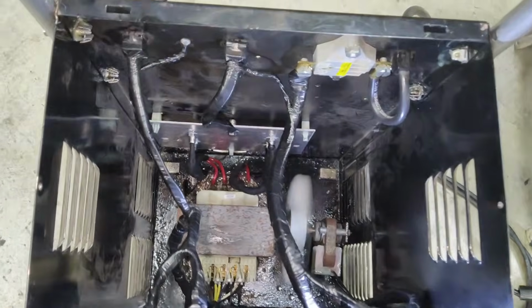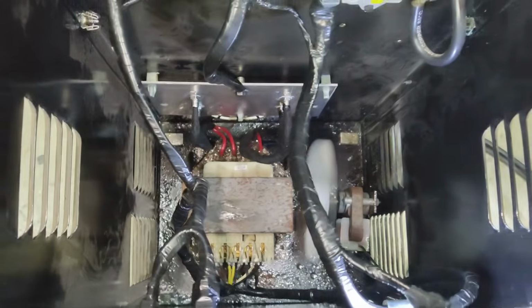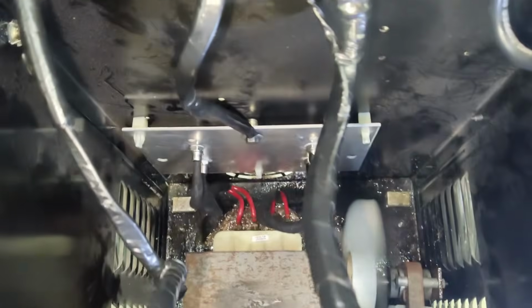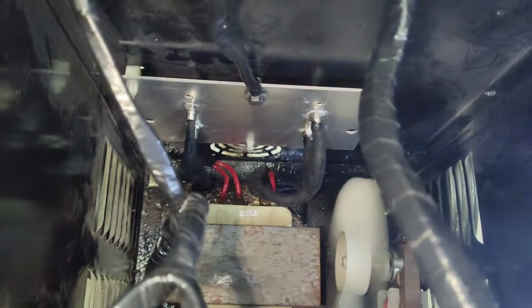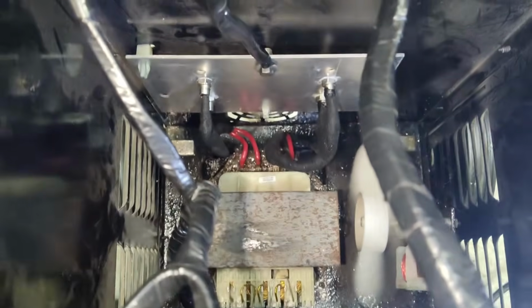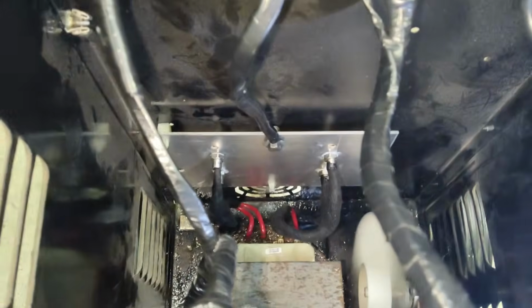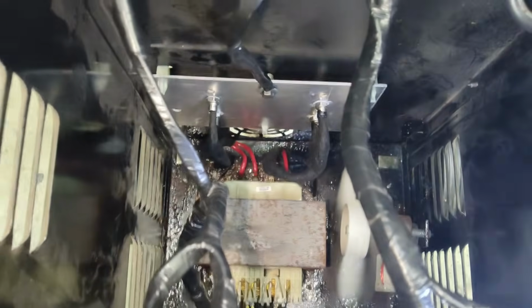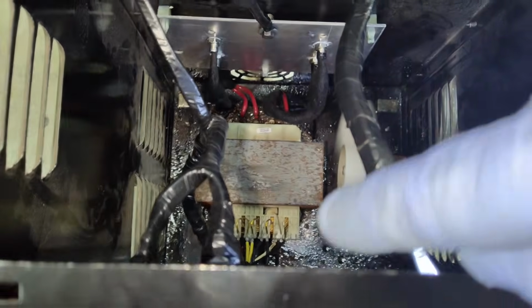If you are having an issue with your charger, they're fairly easy to diagnose on this. If you've got power coming out of the transformer, those red wires going to the diodes, you should have AC voltage there. If you don't, there might be something wrong with the transformer, or you might want to check that thermal fuse that's right on the transformer there.